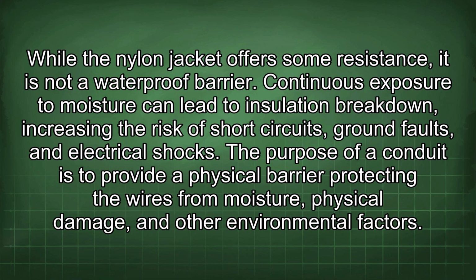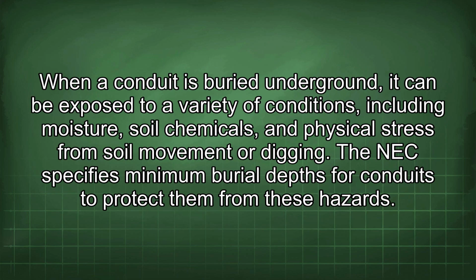The purpose of a conduit is to provide a physical barrier protecting the wires from moisture, physical damage, and other environmental factors. When a conduit is buried underground, it can be exposed to a variety of conditions, including moisture, soil chemicals, and physical stress from soil movement or digging. The NEC specifies minimum burial depths for conduits to protect them from these hazards.